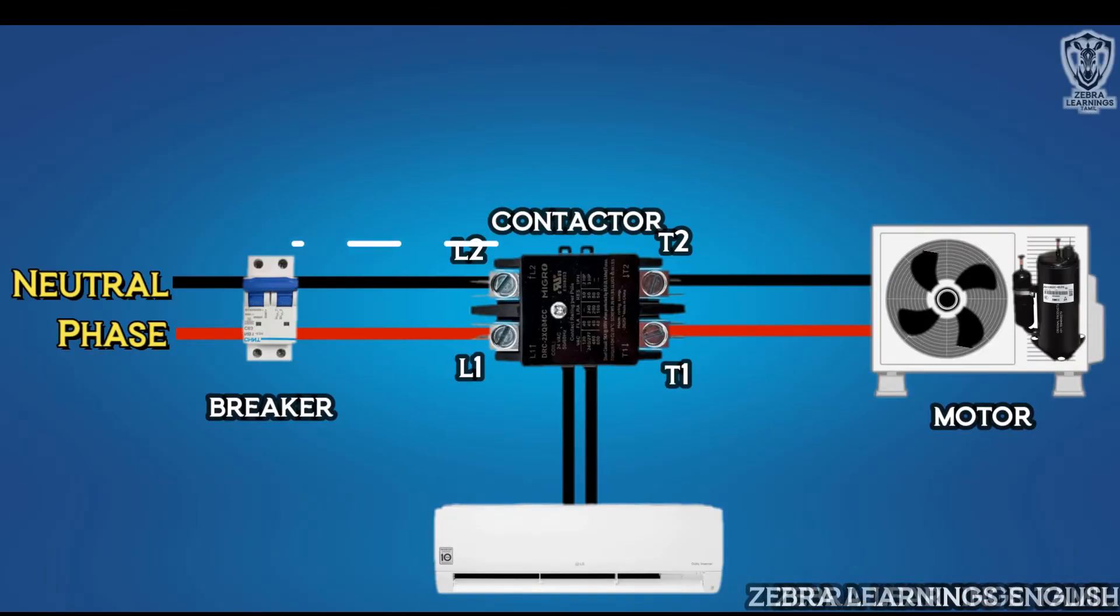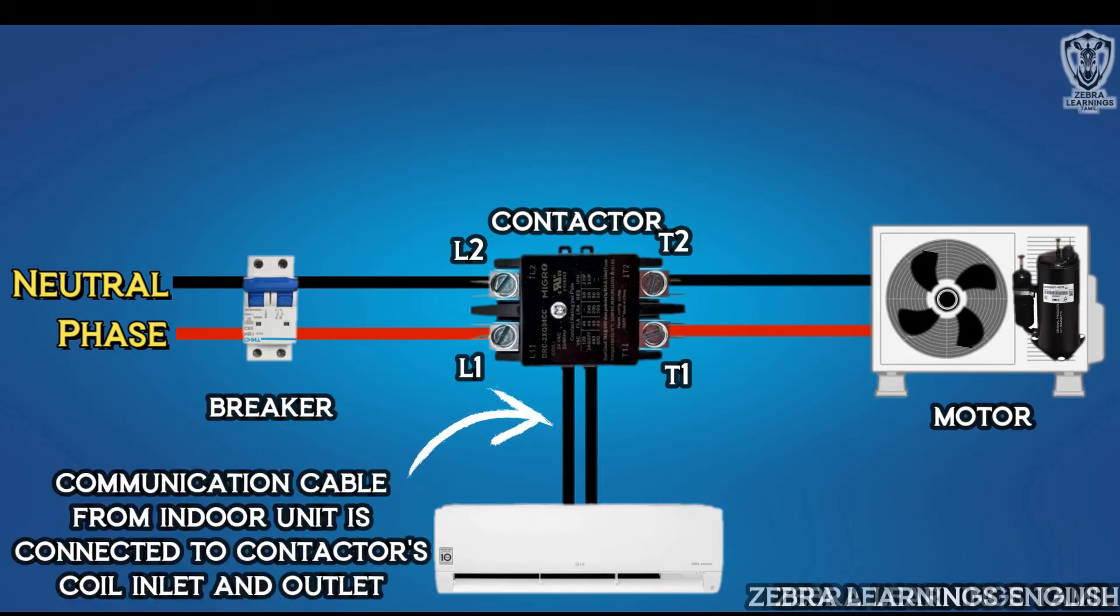It is a two-pole contactor, whose L1 and L2 ports have wires connected from the main power supply. Compressor and fan motor are connected from T1 and T2 ports. Control wires are connected from the indoor unit to the contactor's coil inlet and outlet port. This is the wiring connection of the contactor in the outdoor unit of the AC.